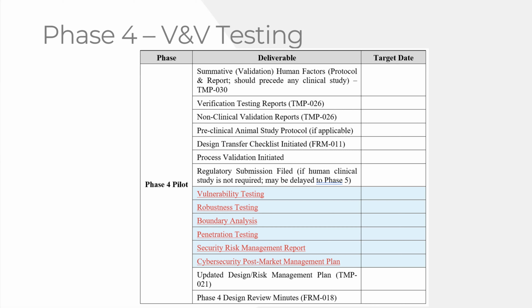Next, we have software validation. We call it validation, but it's really verification, making sure that all your software will meet the SRS requirements, software requirement specs. That would include unit testing, integration testing, and then system testing. Next, we would have the electrical safety and EMC testing. This is verifying the device meets the requirements for electrical safety and electromagnetic compatibility. And there might be other tests that are particular to your device, like electrode testing, if you have a TENS device.